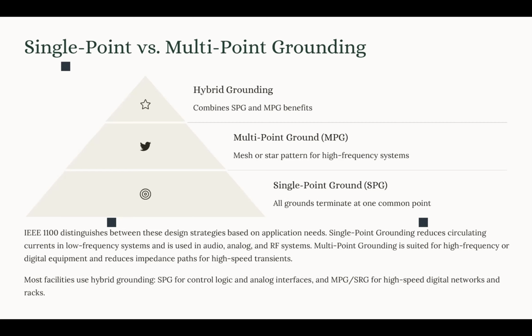But there is a limitation. When we are dealing with high frequency, we are going to see high impedance in those single point grounding systems, because we have long ground leads which will act like an inductor, and we know the impedance of an inductor is j omega L. So longer distances, longer grounding paths, meaning higher L, meaning higher impedance. When we increase the omega, the frequency, then that impedance also will increase. So single point connection has a vulnerability when we talk about the high frequency range.